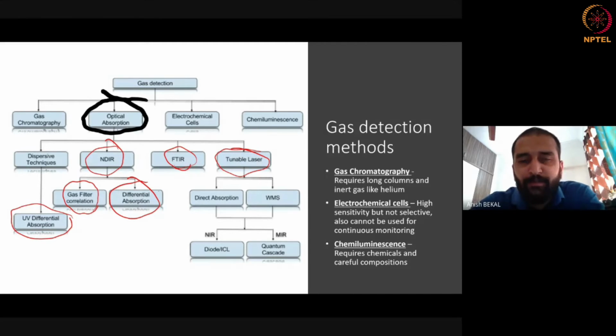And then you have Fourier transform infrared spectrometer, which basically uses a Michelson interferometer to move a particular mirror to generate correlations or interference at different spectrums, which will lead to generation of the spectral profile. From this spectrum, you can determine - it's actually a very, very high resolution method, and typically labs use them to get a good approximation of the actual lines that exist. So you have FTIR. But in the field, there are very few instruments which use this method, primarily because there are moving parts and there's a lot of maintenance involved.